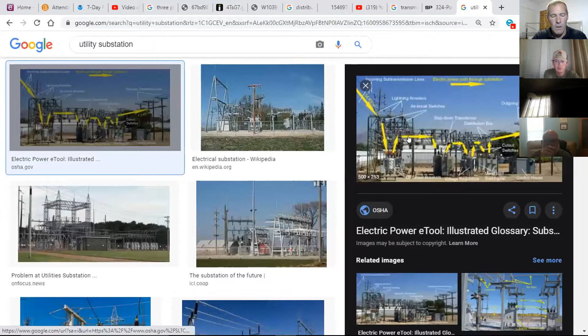So they're coming in with 3 conductors delta into a protective breaker, going over to the transformer, and guess what's happening at the transformer? Before, I showed you an image on my screen, and that image of transformation was Y-Y. I had Y input on my primary side, and I had Y output on my secondary side. What is the transformer doing in this substation? In delta, out Y. There you go. It's happening at transformation at the substation. My wiring configuration in the transformer is input delta, output Y. Once I go output Y from this point out to my distribution system at 7,200 volts, I now include a neutral.